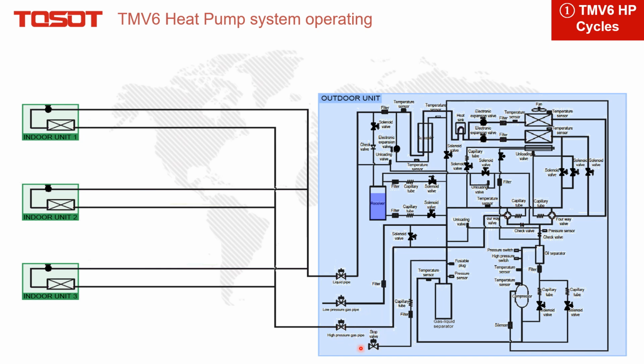And this is the low pressure check valve. It just connects to here, which is the gas liquid separator. Besides, here is the compressor, the oil separator, and there are two four-way valves. And this one is the outdoor heat exchanger. There are two EXVs for this outdoor unit. And this is the heat sink. The purpose of it is just to absorb the heat from the compressor driver board. And this is the subcooler. It's actually a plate heat exchanger. And here is the accumulator, also called the receiver. The purpose of it is just to optimize the refrigerant flow amount. Okay, I will show you how the refrigerant flows for your better understanding.